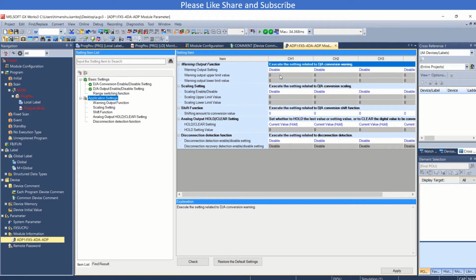Now these are the settings which you might have to do, or if you want you can use the other settings also, like warning output signal setting and this scaling, like you want to use 0 to 10 as 0 to 1000 or 0 to 200 or 0 to 500, so you can work out accordingly here. And this is the disconnection enable setting. So if in any case the output is disconnected, it will generate an error.